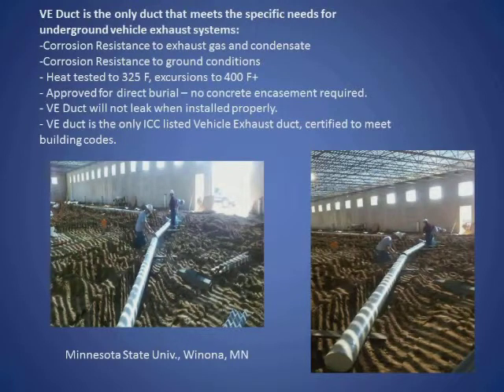VE duct is the only duct that meets the specific needs for underground vehicle exhaust systems. It's corrosion resistant to the exhaust gas and condensate. It is corrosion resistant to the ground conditions, which can be acidic or caustic, especially if there's moisture around. It's heat tested to 325-degree excursions to 400 plus. It's approved for direct burial, no concrete encasement required. VE duct will not leak when installed properly. It's been tested. VE duct is the only ICC-listed vehicle exhaust duct certified to meet building codes.